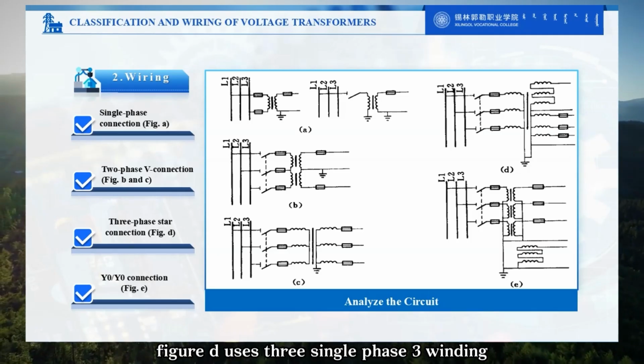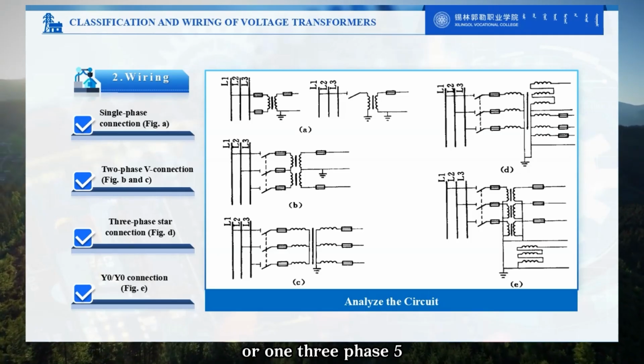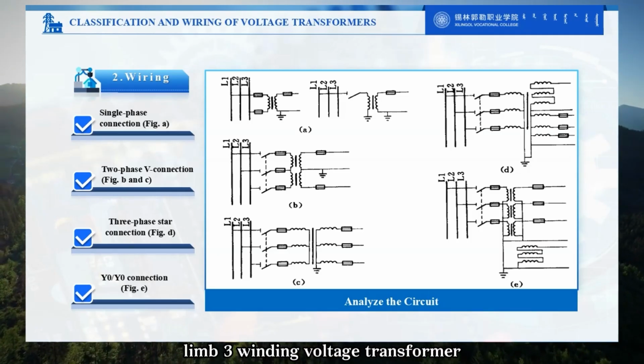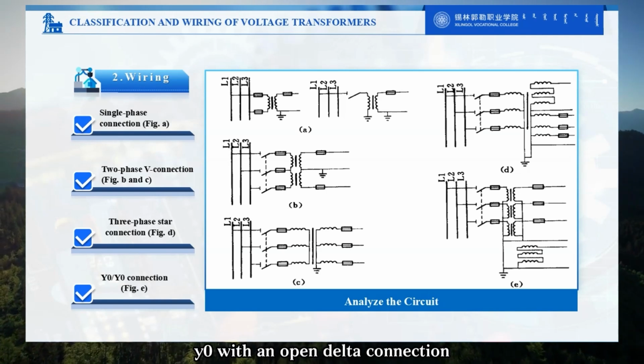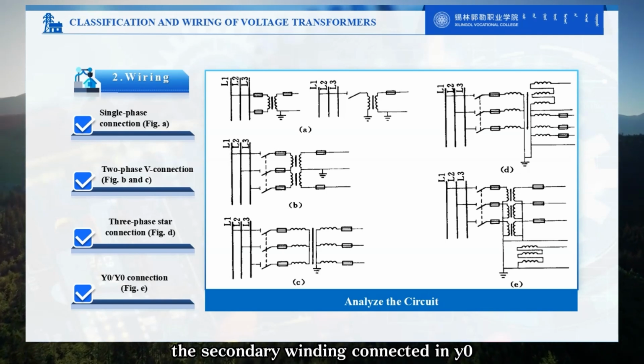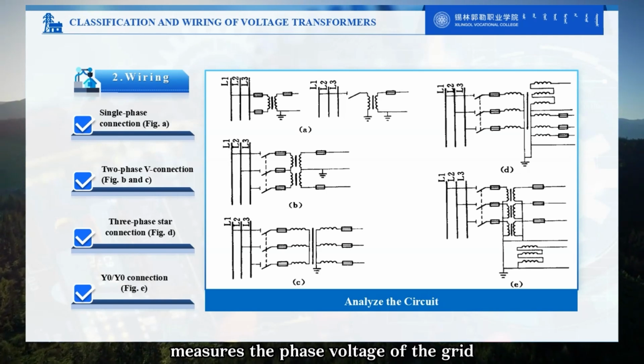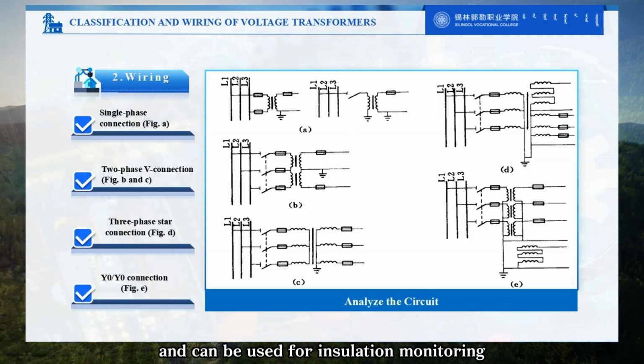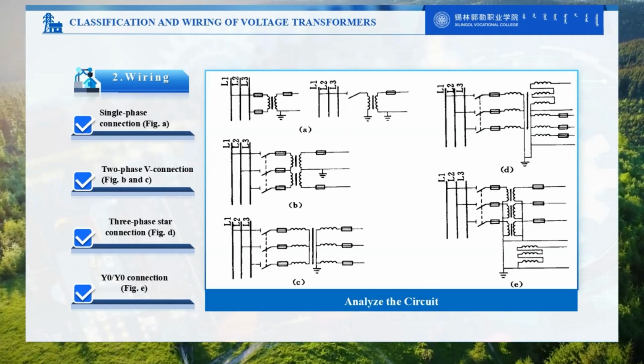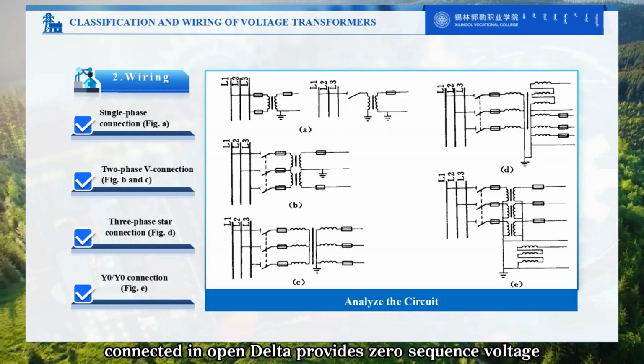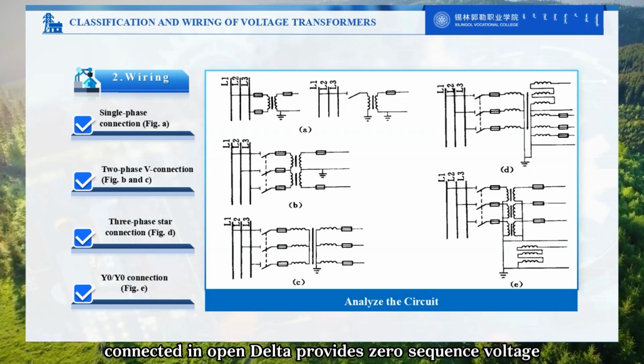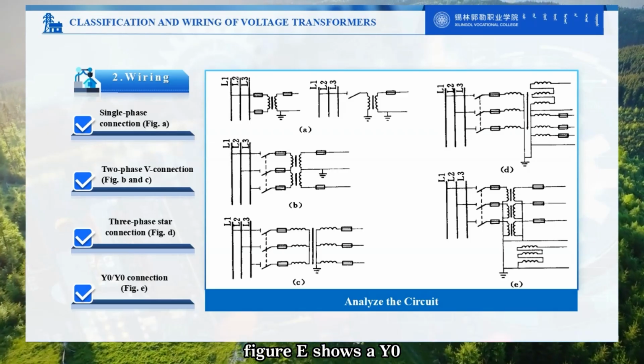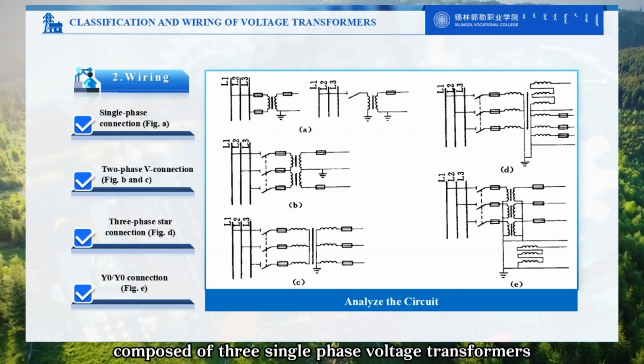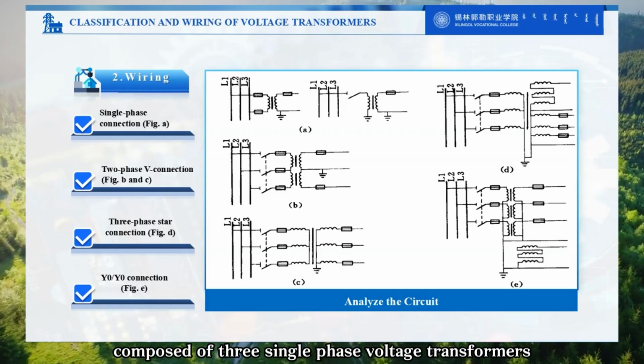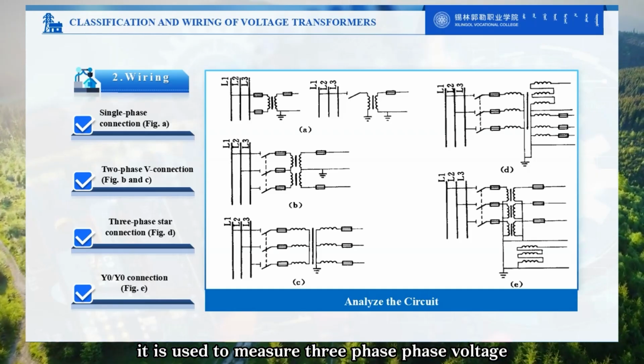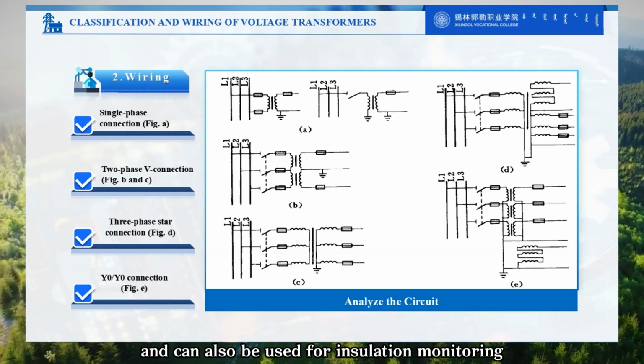Figure D uses three single-phase three-winding or one three-phase five-limb three-winding voltage transformer connected in Y0Y0 with an open delta connection. The secondary winding connected in Y0 measures the phase voltage of the grid and can be used for insulation monitoring. The auxiliary secondary winding connected in open delta provides zero-sequence voltage. Figure E shows a Y0Y0 connection composed of three single-phase voltage transformers. It is used to measure three-phase voltage and can also be used for insulation monitoring.